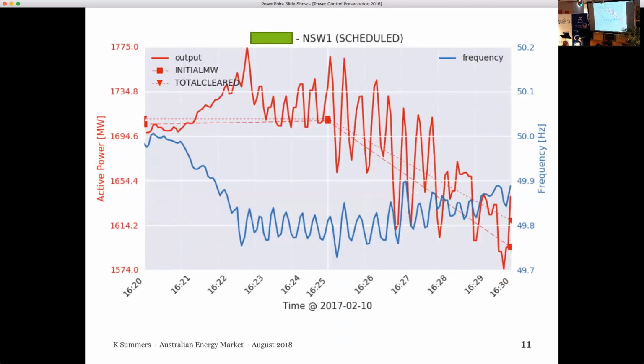Why? Because the units themselves want to respond physically to what they're coupled to, but their control system is telling them to do something else because the market says so. It's going down here to where the market says so. The frequency has not recovered, but it is reducing its active power.